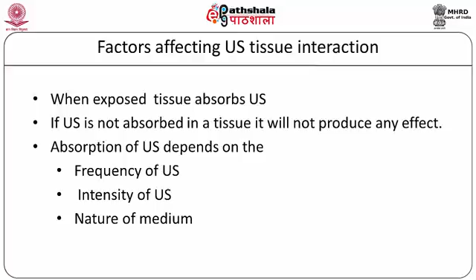The frequency of ultrasound influences the absorption and reflection of waves. These processes produce loss of energy contained within a beam of ultrasound as it travels further from the source. This phenomenon is known as attenuation, and it is explained by the concept of half-value distance. The depth at which the energy of ultrasound is reduced to half of its original value is known as the half-value distance. At 3 MHz, the acoustic energy in tissue is reduced to half within 1.5 cm, whereas the half-value distance at 1 MHz is about 5 cm. The half-value distance is an indication of the penetration ability of ultrasound.